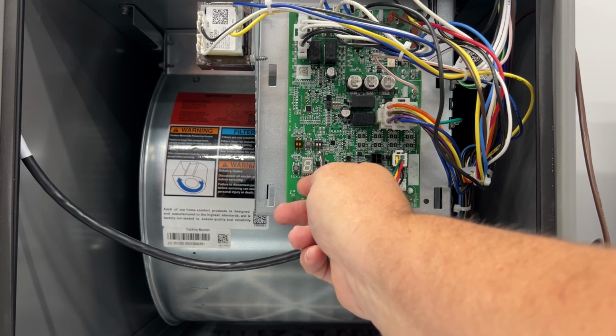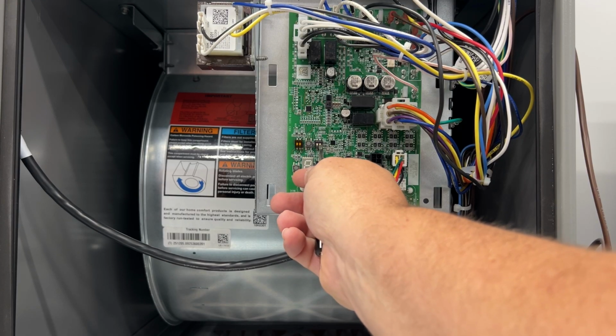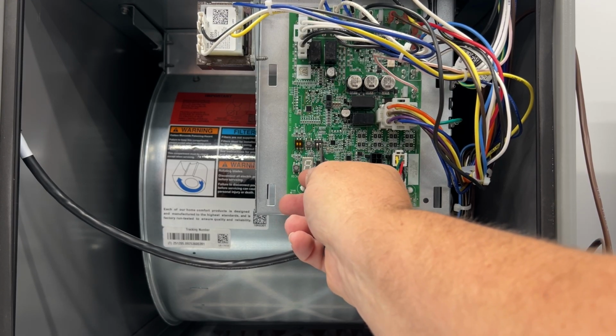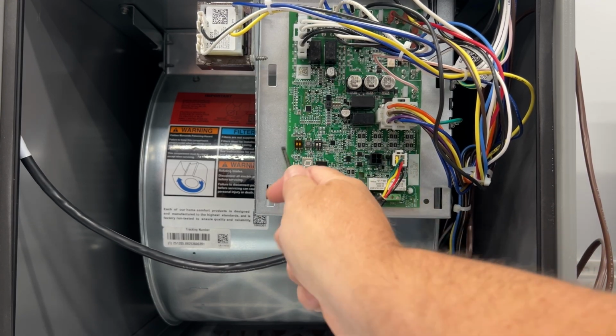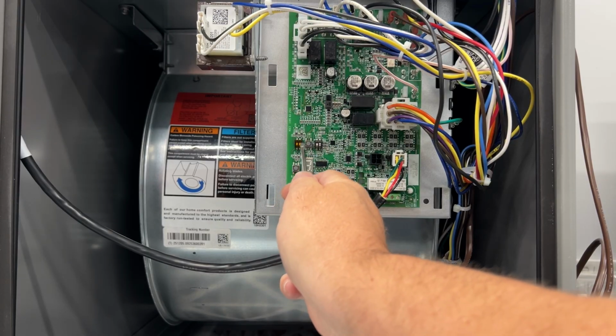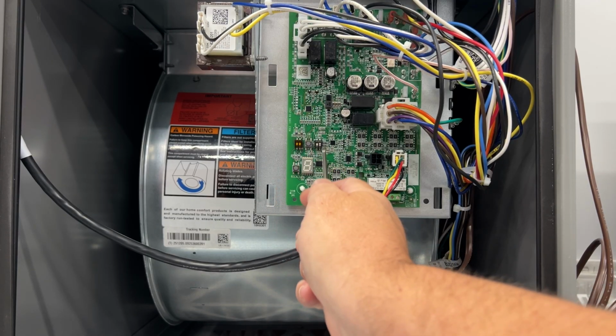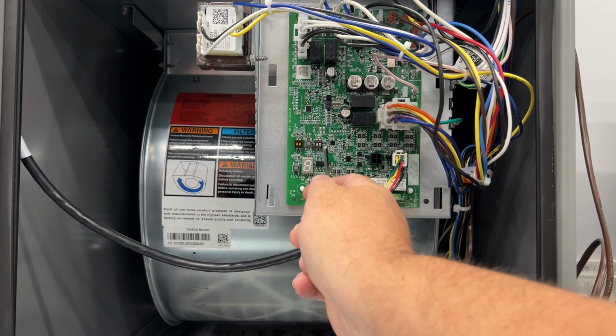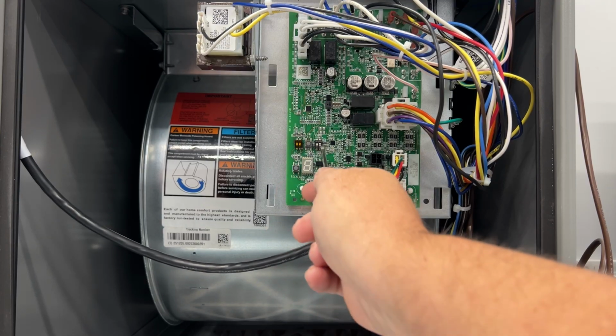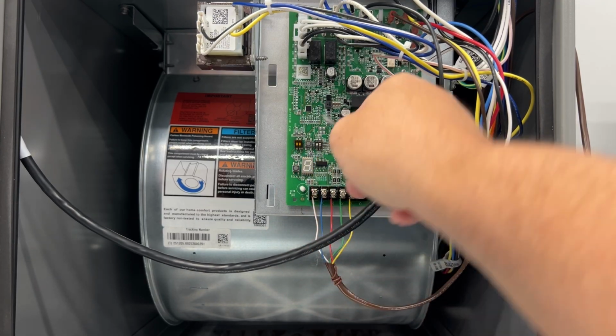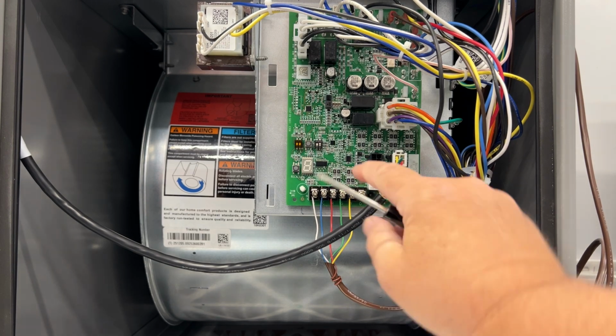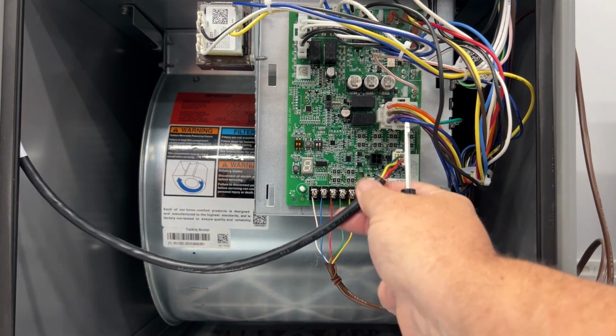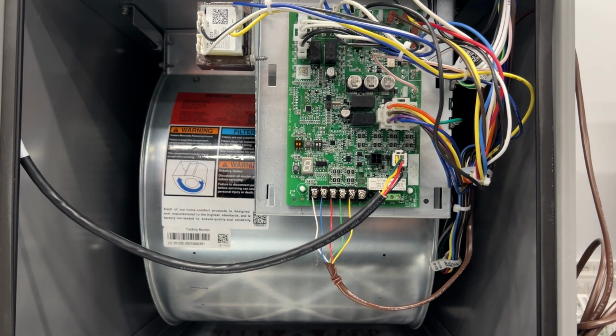Okay, so on number 2, we're actually going to disable number 2 by pushing that switch up. You will have a little rubber coating that kind of peels off, but you can actually push these switches up through that rubber coating there. And then leave number 1 in the down position. That's going to show that this board actually has a sensor on that location.